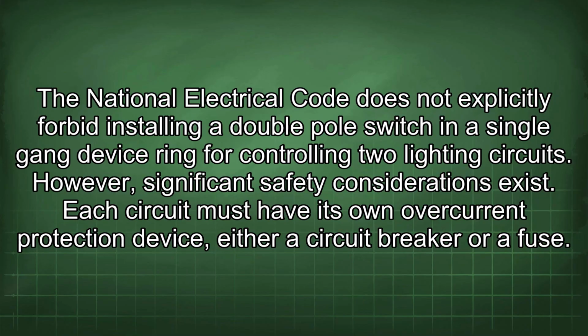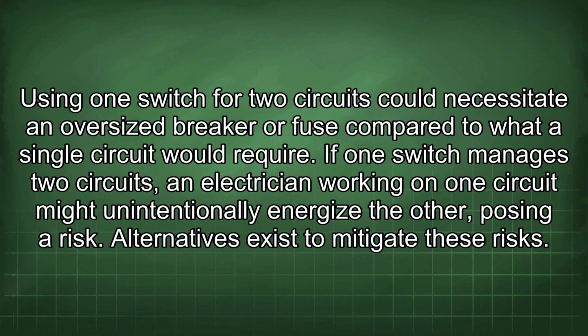The National Electrical Code does not explicitly forbid installing a double-pole switch in a single-gang device ring for controlling two lighting circuits. However, significant safety considerations exist. Each circuit must have its own overcurrent protection device, either a circuit breaker or a fuse. Using one switch for two circuits could necessitate an oversized breaker or fuse compared to what a single circuit would require.